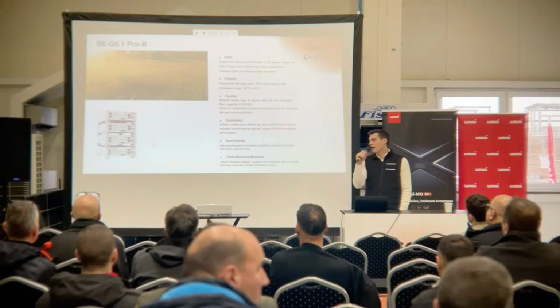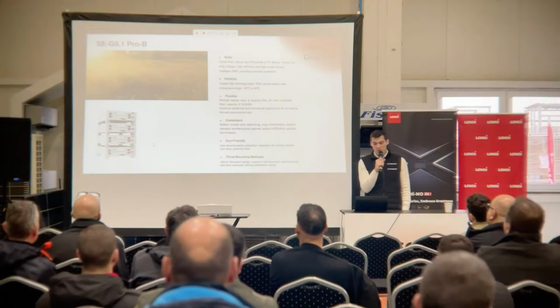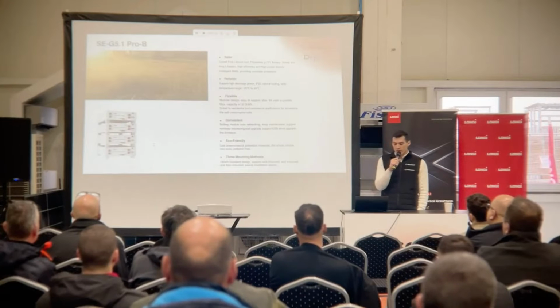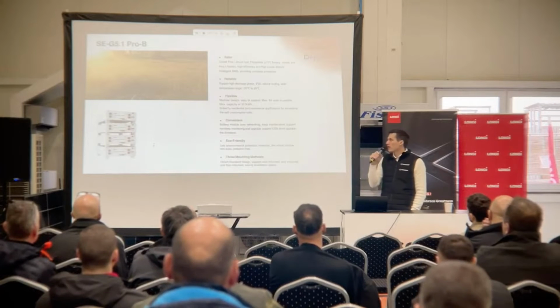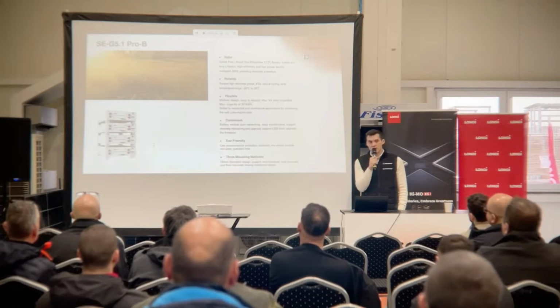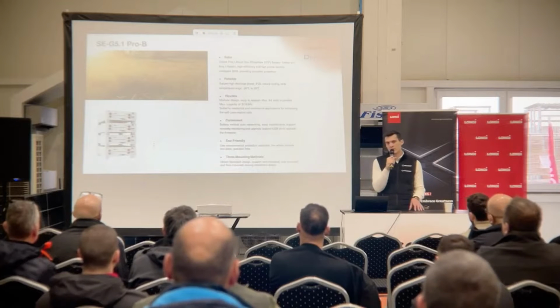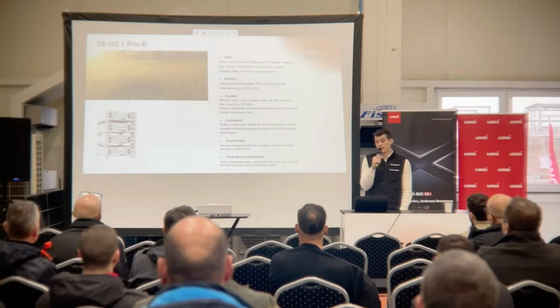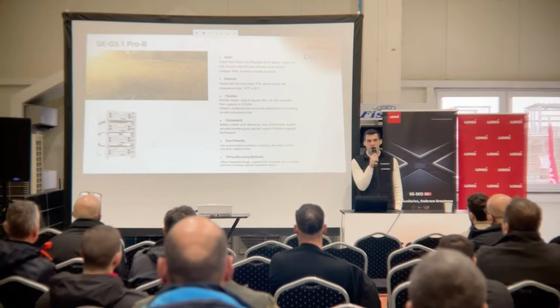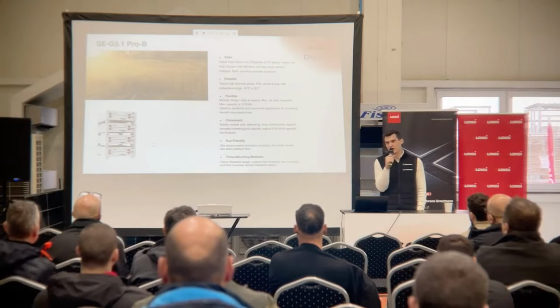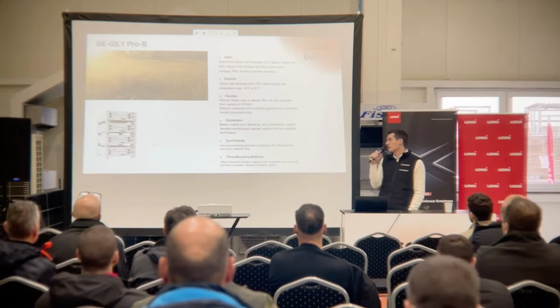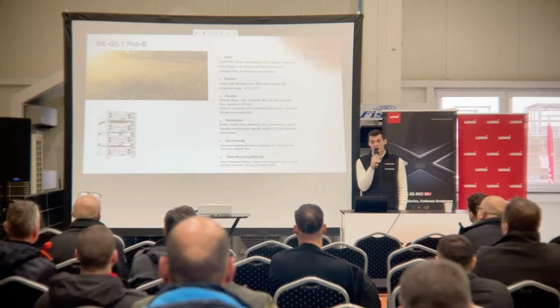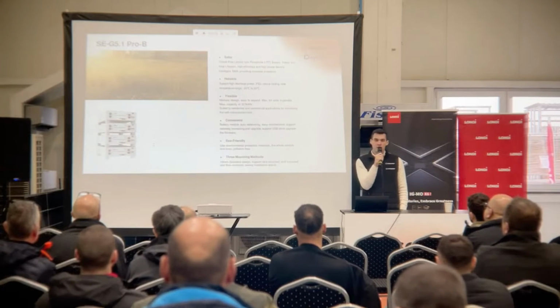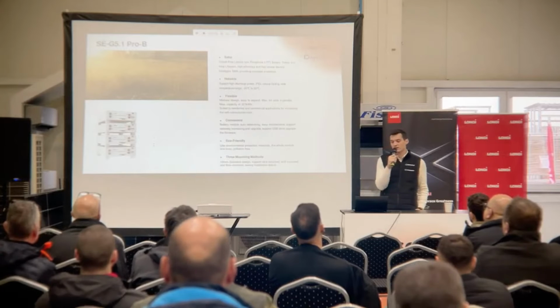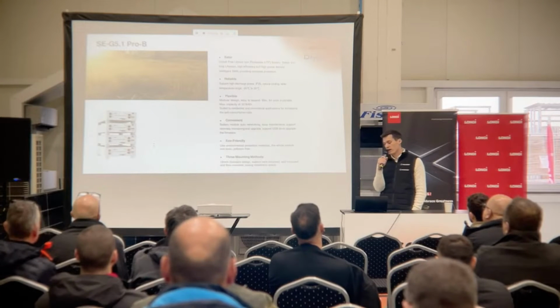It's only IP20, so you have to install it indoors. It's important to pay attention that you don't put it outside, because if the temperature drops below 1 or 0 degrees Celsius, the batteries will not be able to charge even from the grid. So it's not just that the inverter won't be able to charge them, but even from the grid they will not be able to charge. And if this state lasts for a long period of time, it could cause harm to the batteries.